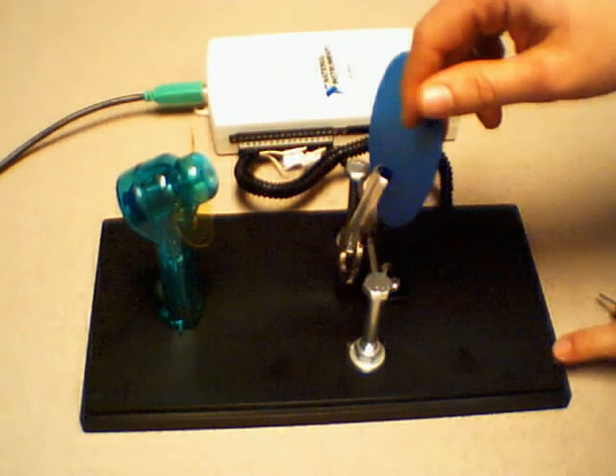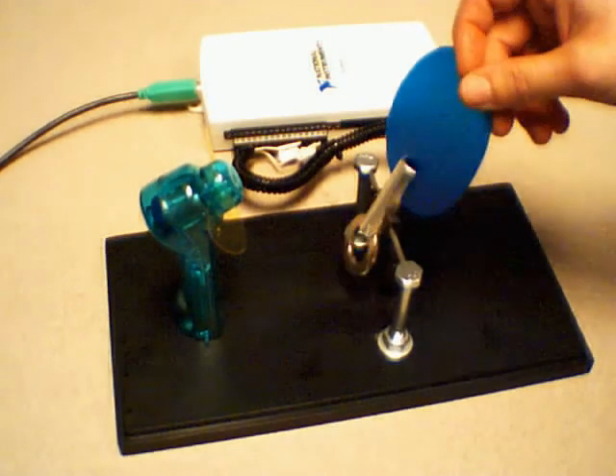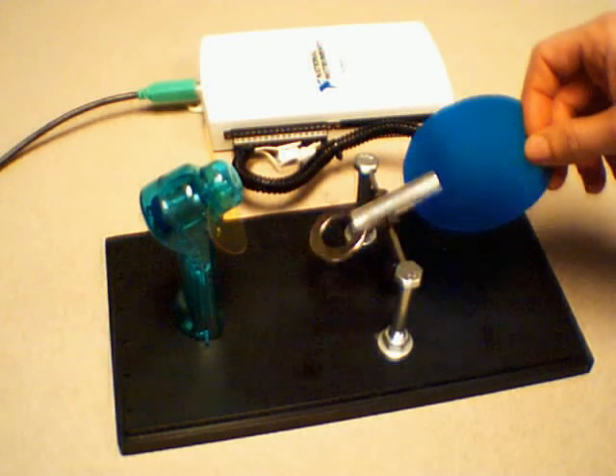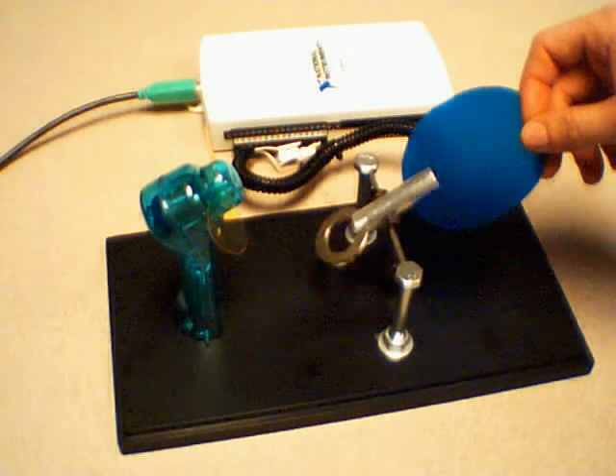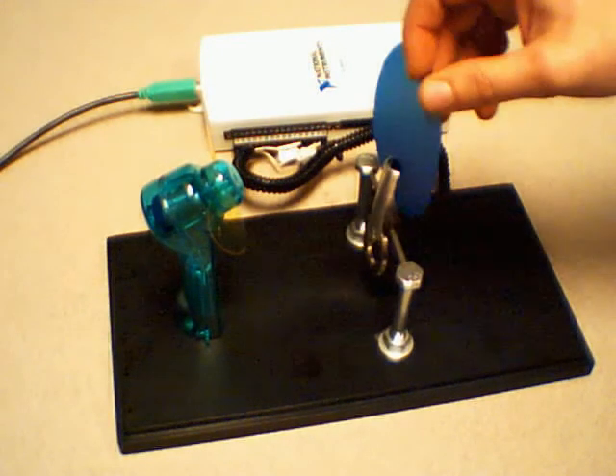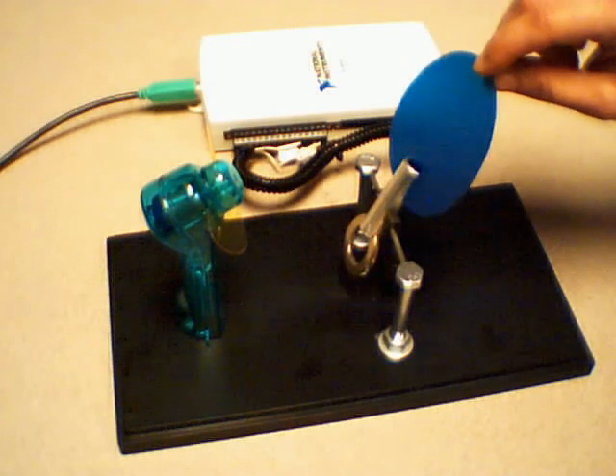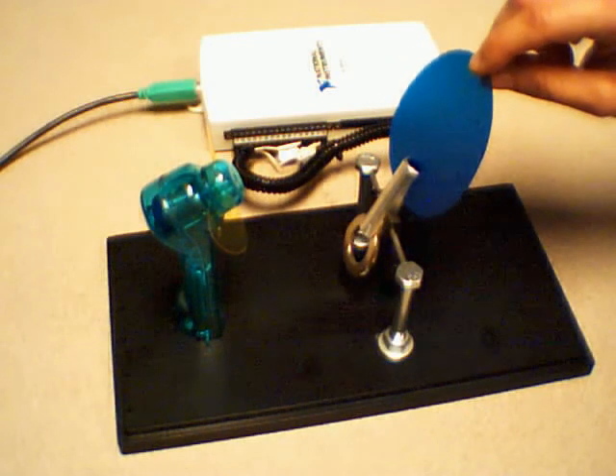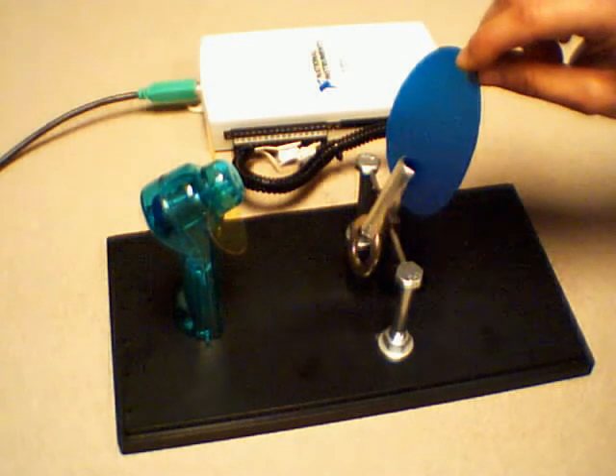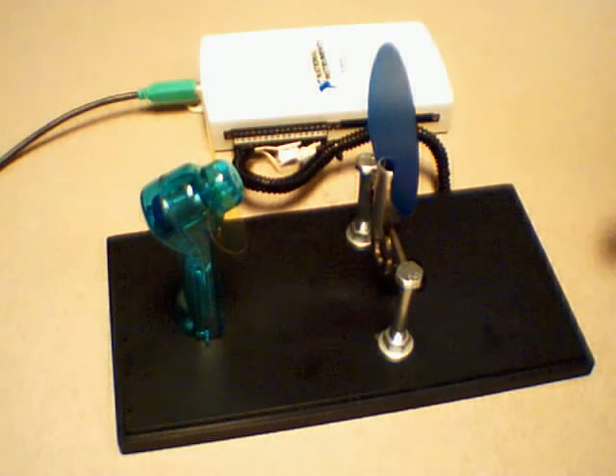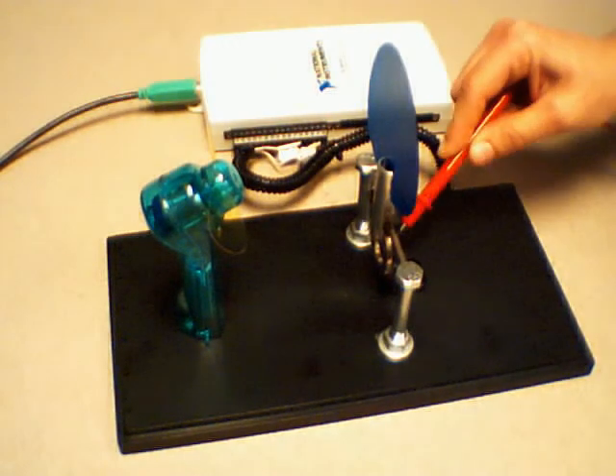If you look on the end of the deflector, we've got that little donut. That's a pretty strong magnet. So depending on where this is positioned, it'll change the magnetic field and essentially change the voltage coming out of the Hall effect sensor down here.